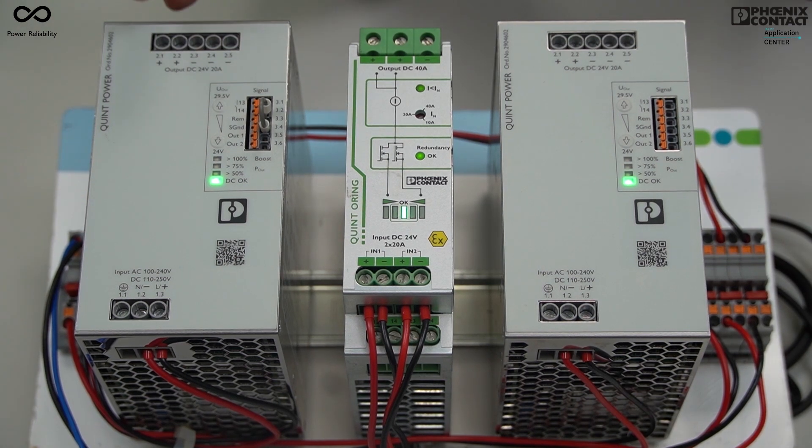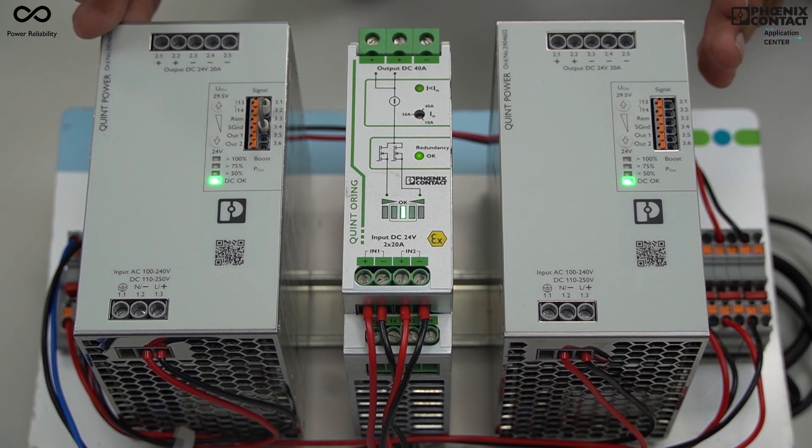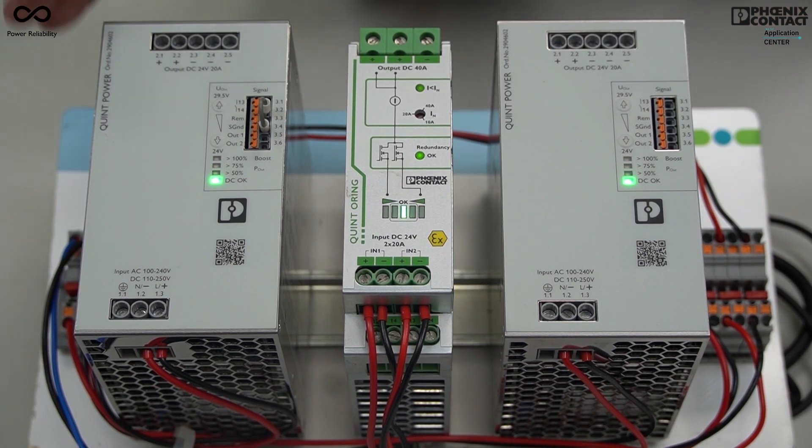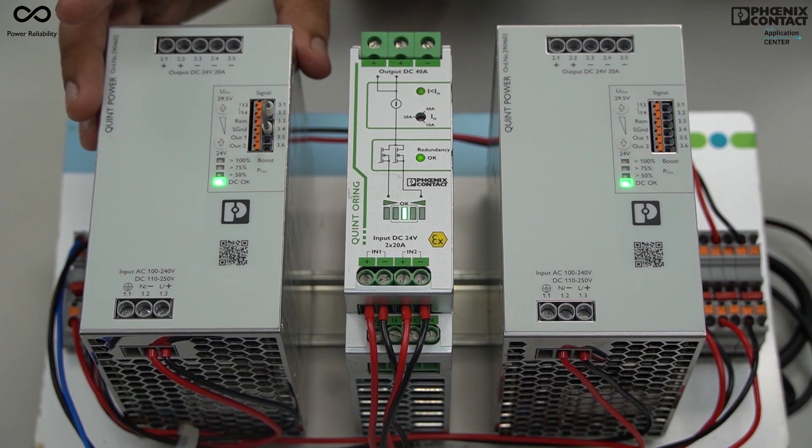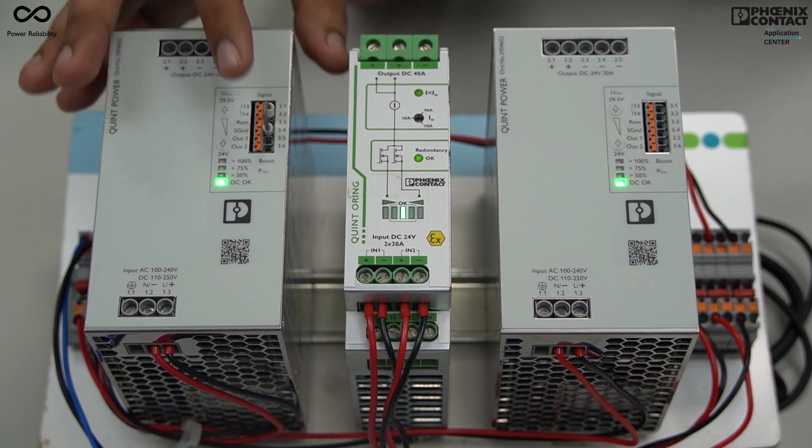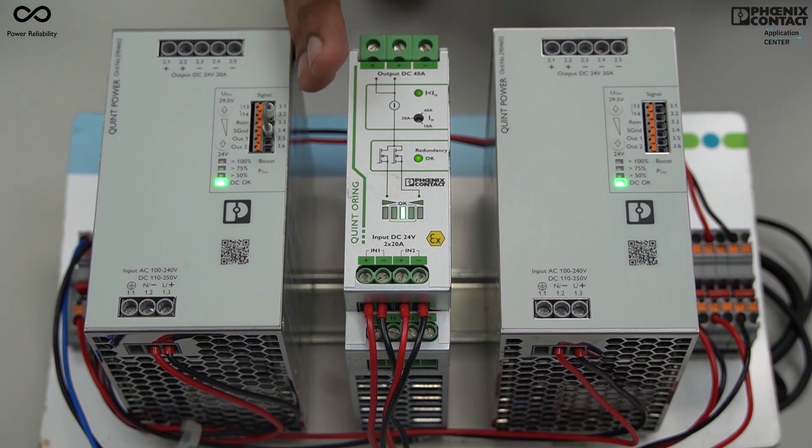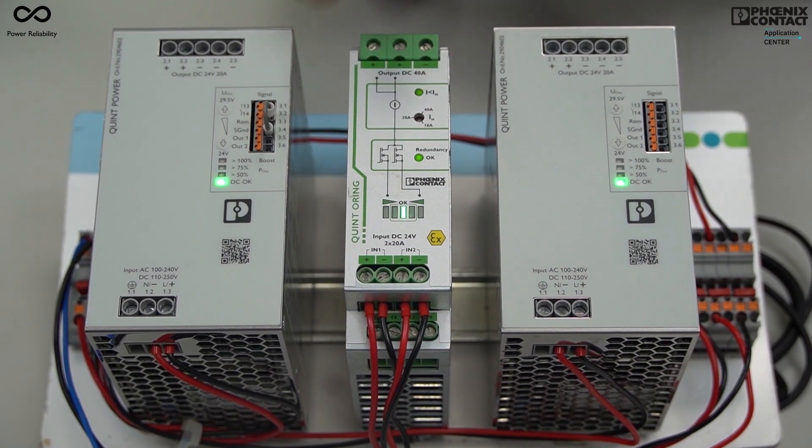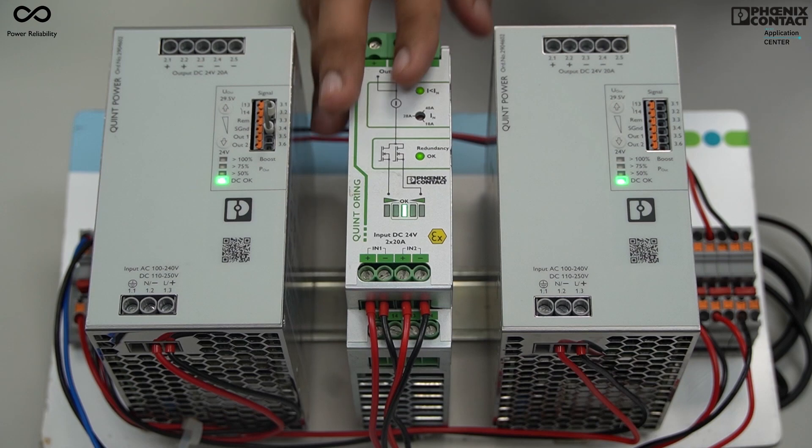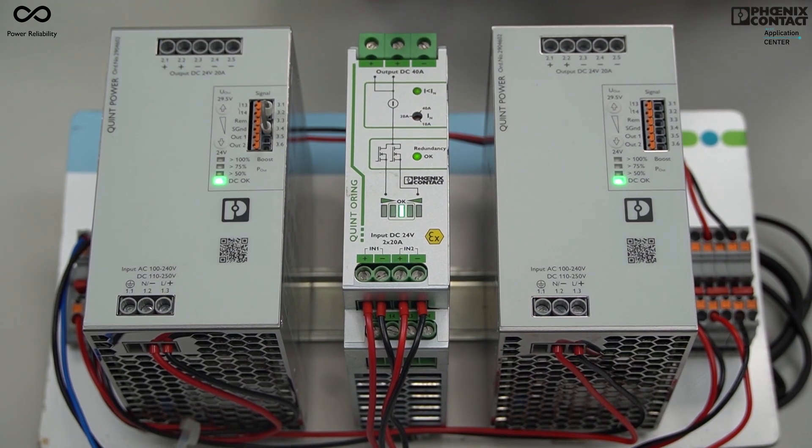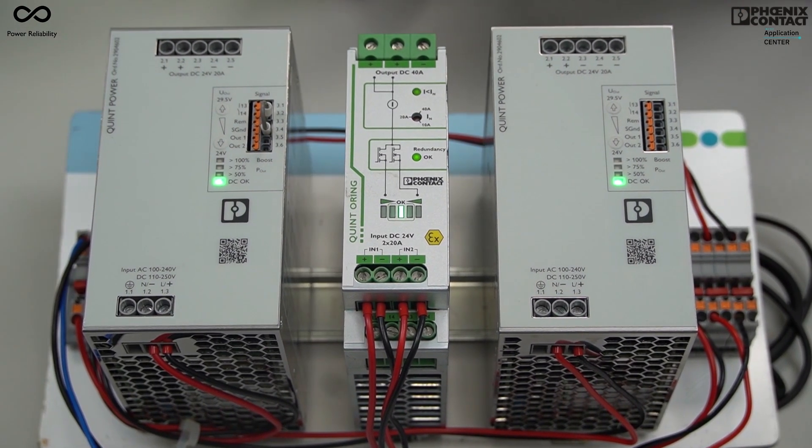Now we will create a faulty condition in this redundant system. We will short the first power supply and switch it off remotely, and then you can see you will get the indication from the power supply as well as the redundancy module while your uninterrupted load will continue working.